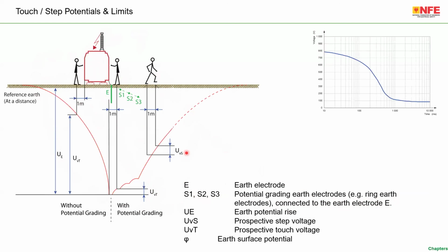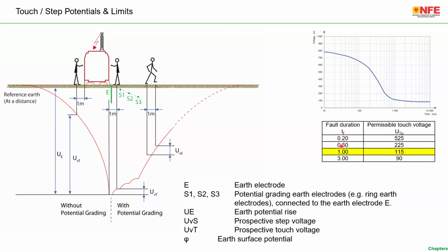What is the limit of touch voltage? Yes, of course, it is given for 1 second. Maximum touch voltage is 115 volt. Now, to reduce the touch voltage, what should we do? S1, S2, S3, which are called the potential grading electrodes. On the other side of the transformer, a person who is standing and touching, you see the touch voltage is very high. He will get electrocuted. Whereas with the use of S1, S2, S3, the potential grading electrodes, the touch voltage is limited to less than a safe level. You see UVT.